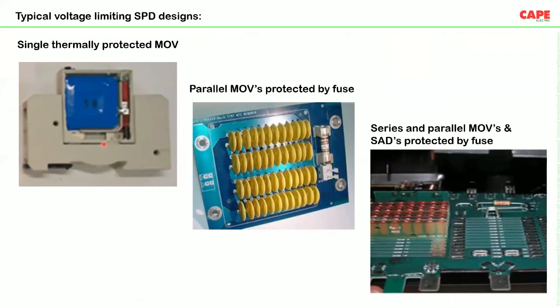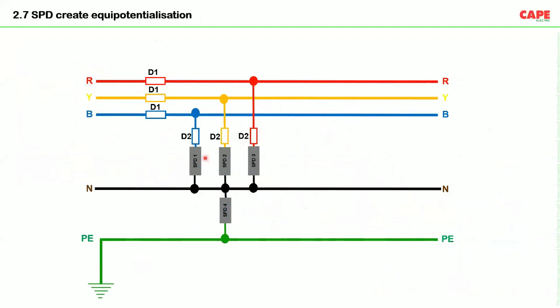So SPDs are made with so many techniques. How it operates is more important for us. Imagine we have the main distribution board, three-phase incoming, neutral incoming, and then you have the PE conductor. So basically on the left side, you have the incoming, and on the right side, you have the installation. Imagine I have 4 SPDs connected in this combination, which we call 3+1. 3+1 means 3 SPDs between the 3 line conductors and neutral, and 1 SPD between neutral and the earth.